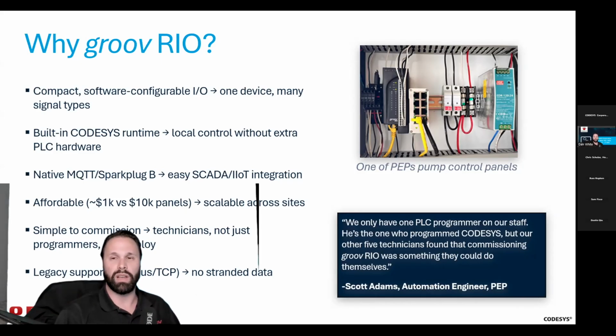Of course, communications was a big part. With Rio speaking MQTT Sparkplug B natively, it made it really simple to tie into their Ignition SCADA. It supports things like store and forward data redundancy to fit their broader IIoT and data collection strategy. And you've also got Modbus RTU and Modbus TCP support, so legacy transmitters already out in the field were covered, and they wouldn't leave any data stranded.